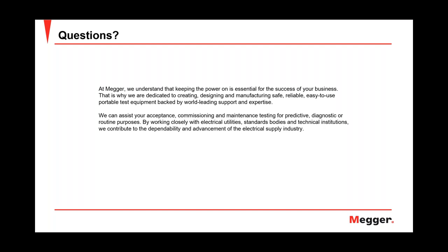Thanks, Jason. Back over to Joseph. Can a TDR show a short on a cable? Can you hear me? Okay. It can show an actual short on the cable, but by a short, it'd be a physical short. That'd be where the concentric neutral or the shield is physically touching the center conductor of the cable itself. And it should show the downward blip right there, showing you that there is an actual short.